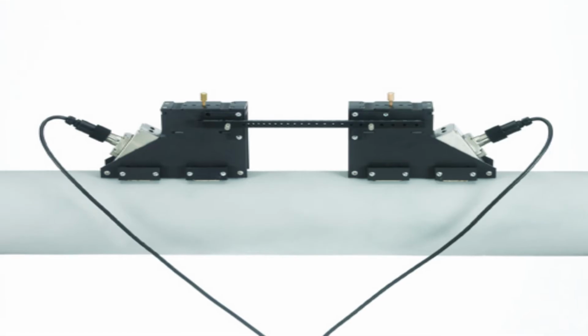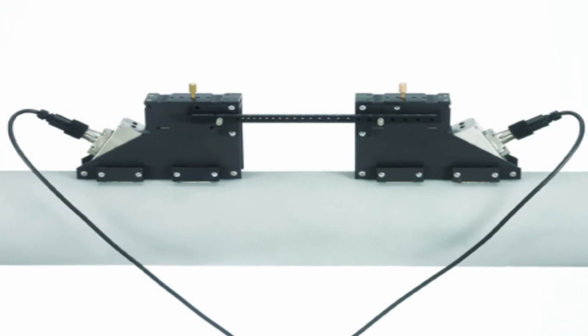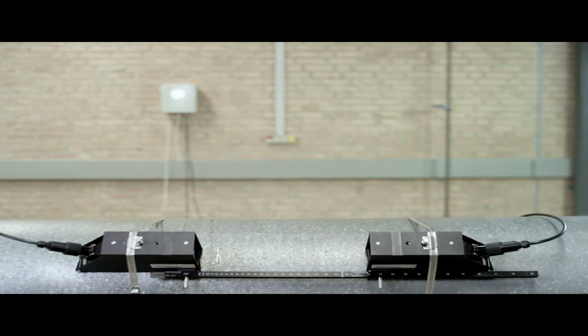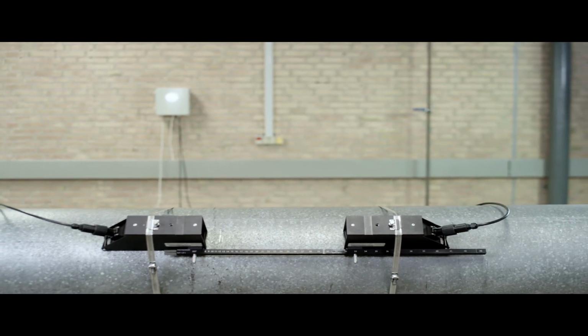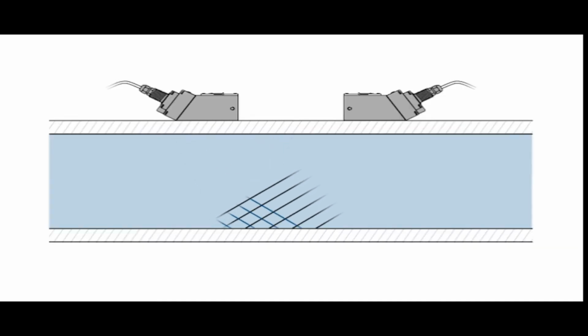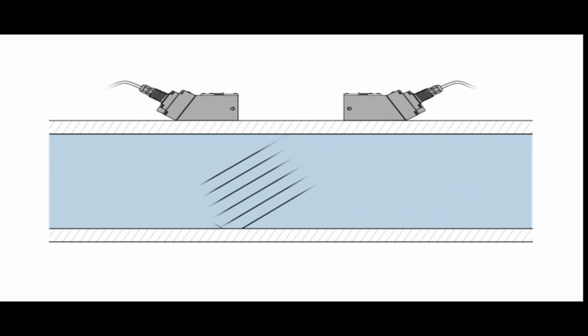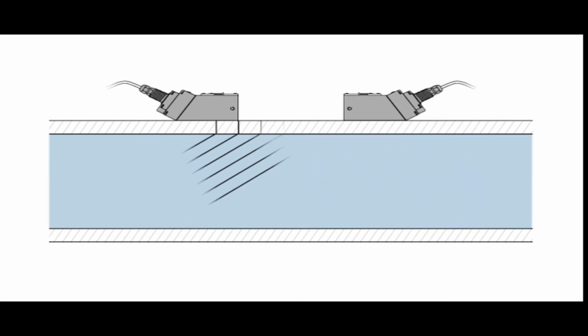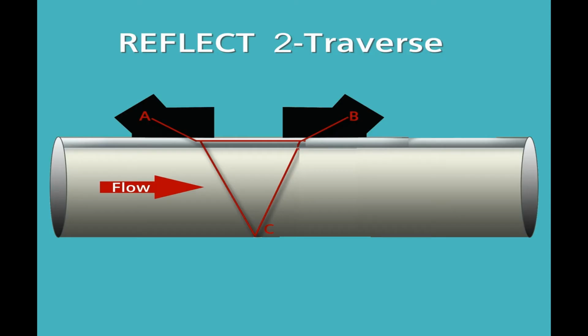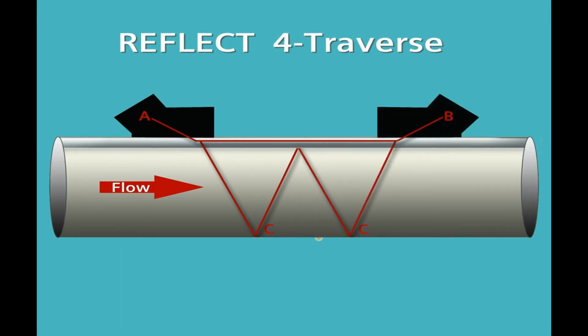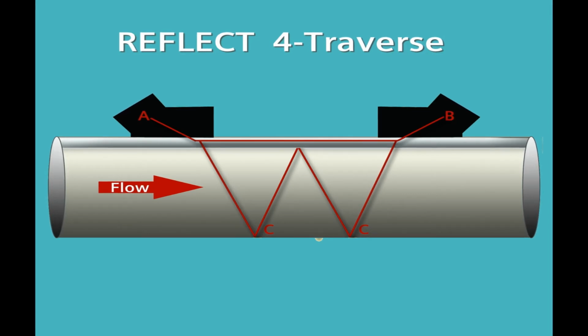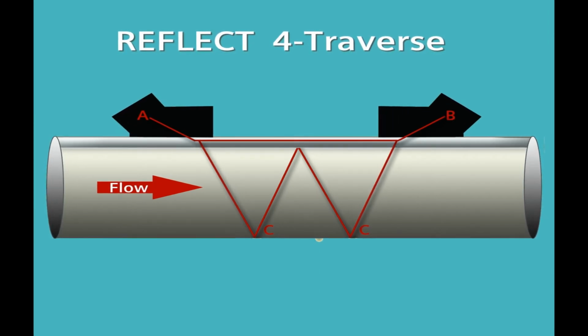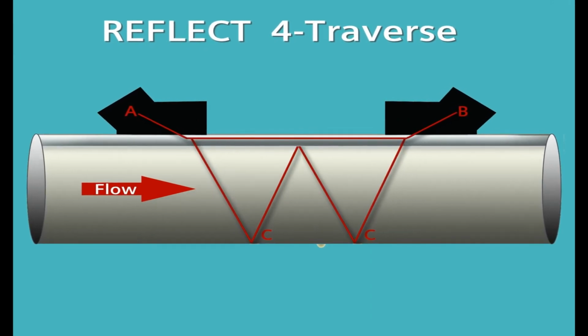The simple answer is, the vast majority of installations should utilize reflect mounting. This method places both sensors on the same side of the pipe. The ultrasonic signal crosses the pipe twice, reflecting off the far pipe wall and thus making 2 traverses across the flow stream. There is also a second type of reflect mounting called 4 traverse. This again places both sensors on the same side of the pipe, but further apart. Now the ultrasonic signal travels across the pipe and back twice, making 4 traverses of the flow stream.